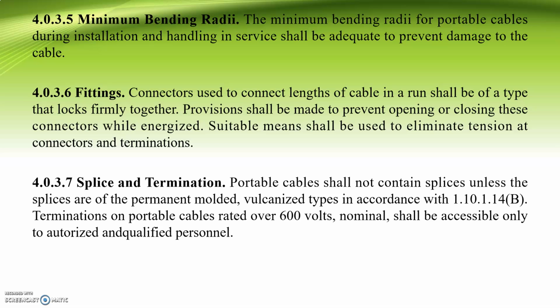Connectors used to connect lengths of cable in a run shall be of a type that locks firmly together. So provision shall be made to prevent opening or closing these connectors while energized. So suitable means shall be used to eliminate tension at connectors and terminations. Chapter 4.0.3.7, splice and termination. So portable cables shall not contain splices unless the splices are of the permanent molded, vulcanized types in accordance with chapter 1.10.1.14 B. Terminations on portable cables rated over 600 volts nominal shall be accessible only to authorized and qualified personnel.